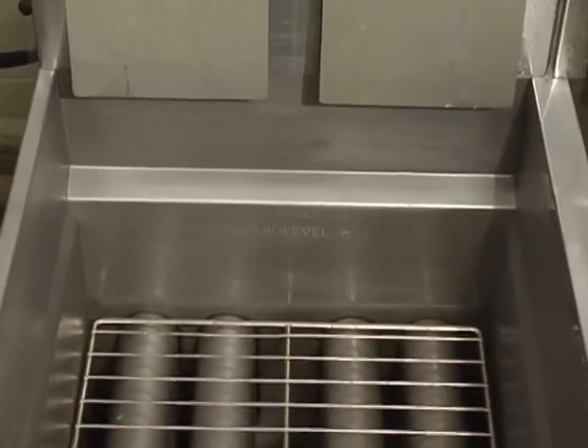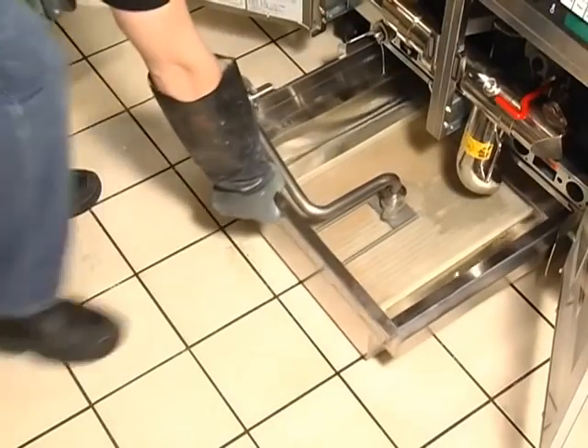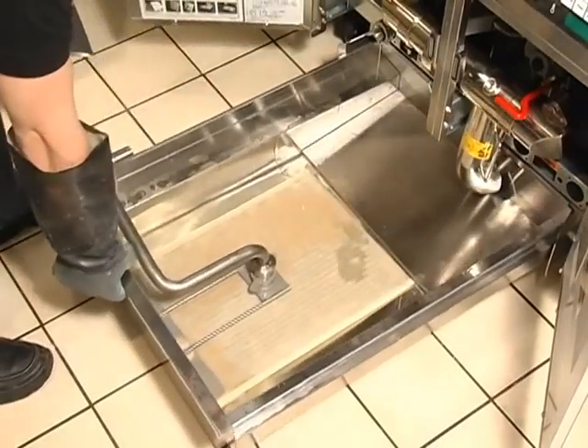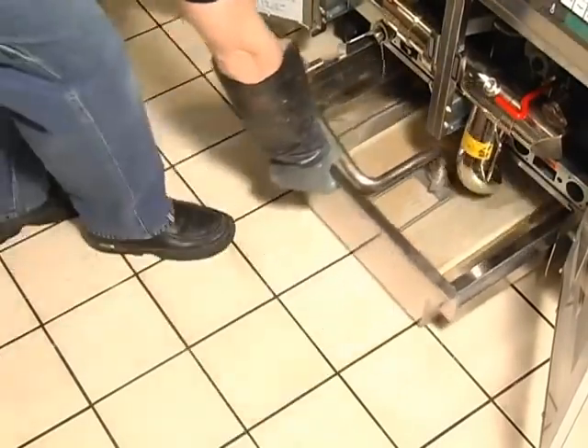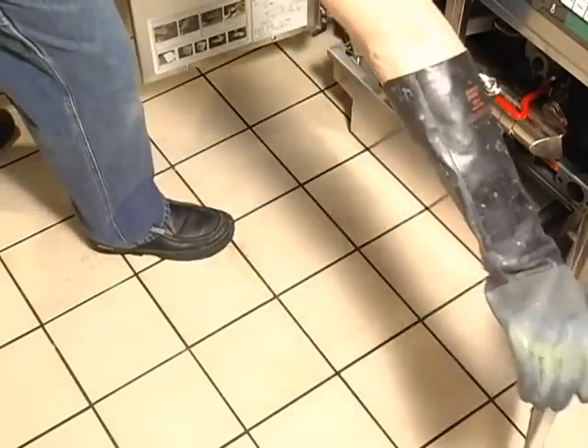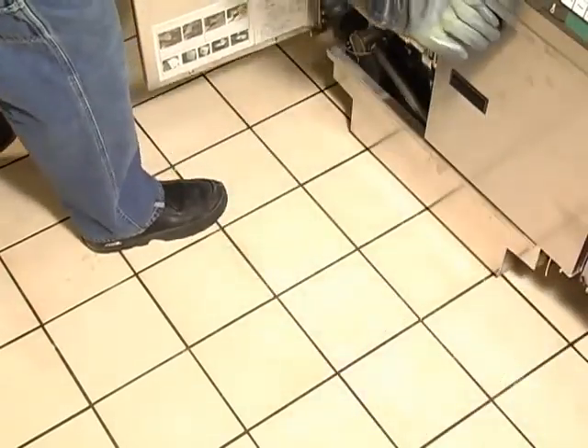Once the oil is still, you'll notice that the oil level is less than when you started. Make sure that it is above the minimum line and below the maximum line. After each filtering, check the paper for large debris or a large collection of crumbs. Remove any debris with the filter crumb scoop supplied with the unit. Be careful not to tear the paper or it will need to be replaced.